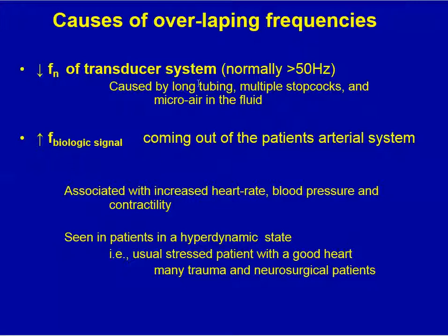Now, the transducer normally has a very high natural frequency of over 50 hertz. Unfortunately, this is markedly degraded by long tubing, stopcocks, and micro air.